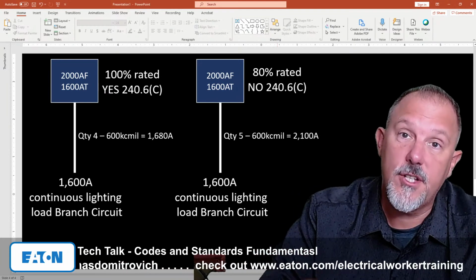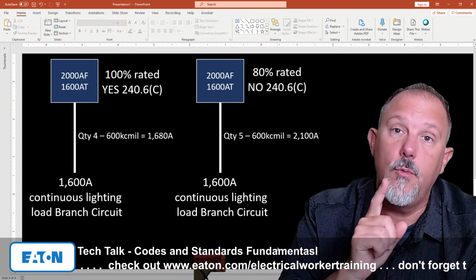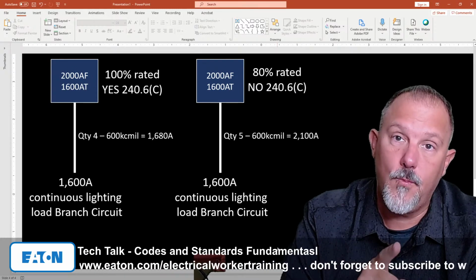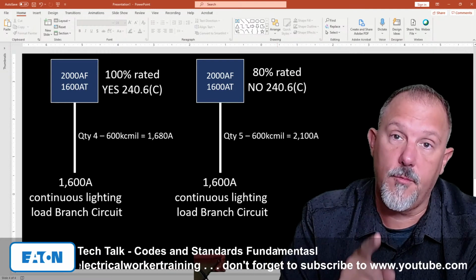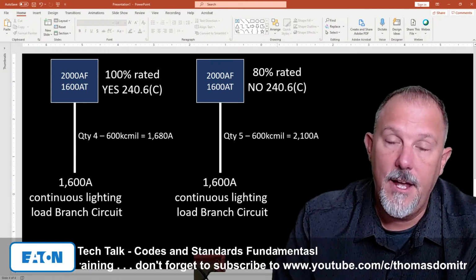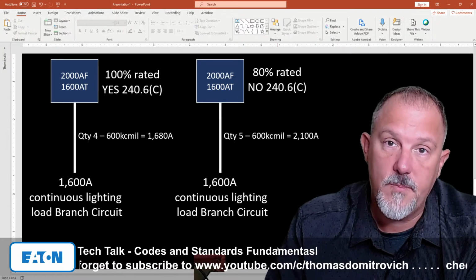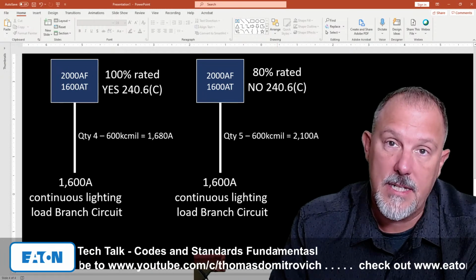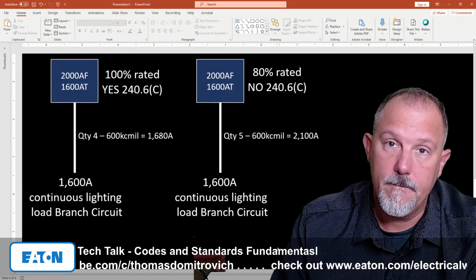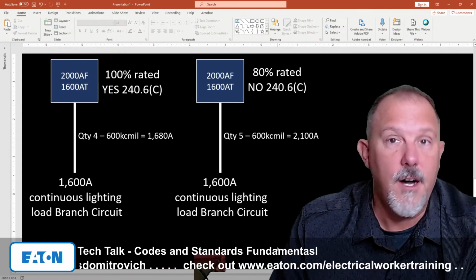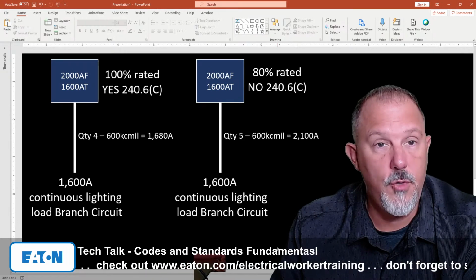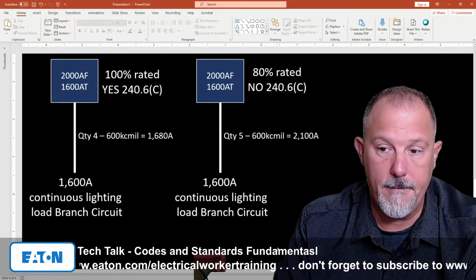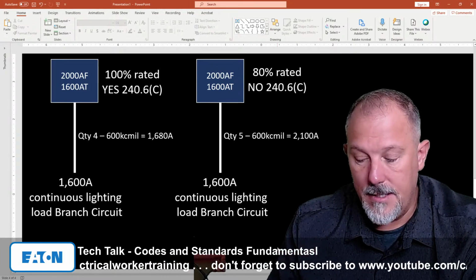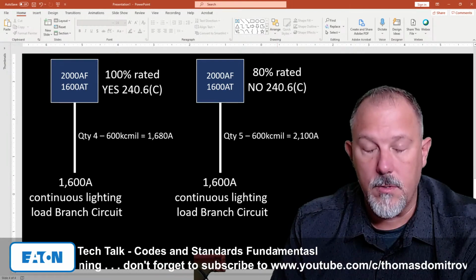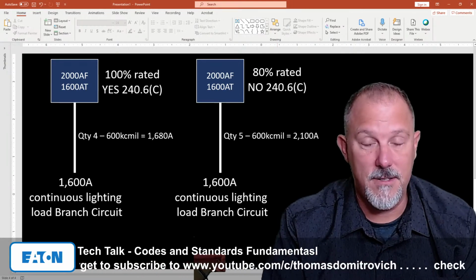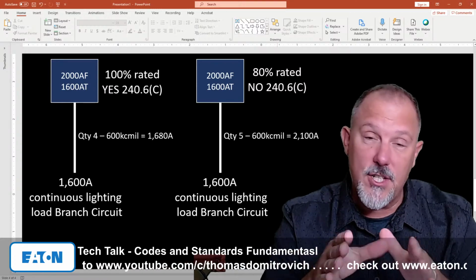But what you don't have in the service is similar language to what is found in 210.20a and 215.3. You don't have the language that says the overcurrent protective device must always be sized at 1.25 times the continuous loads. And that is probably, to John's point, because of the diversity when you're up there at the service. You have a lot of loads that'll come on and go away and come on and go away. So that is another important distinction.